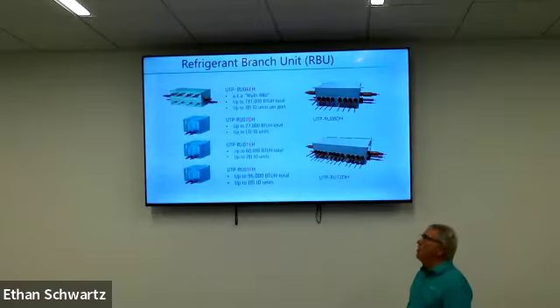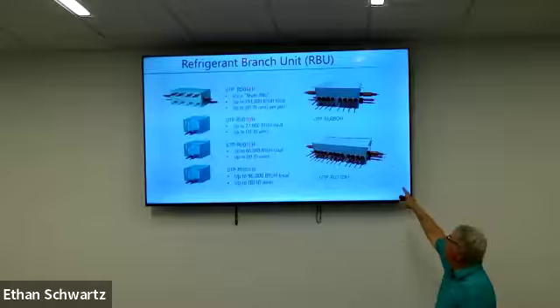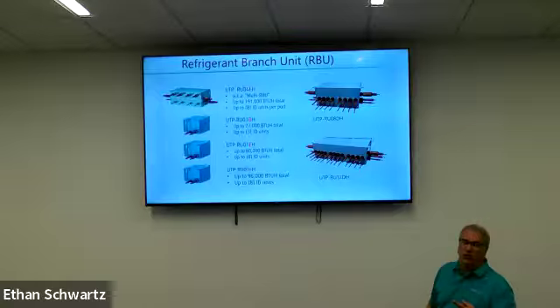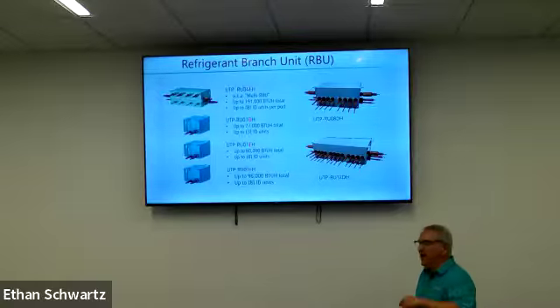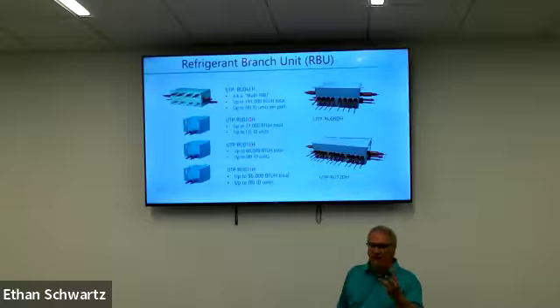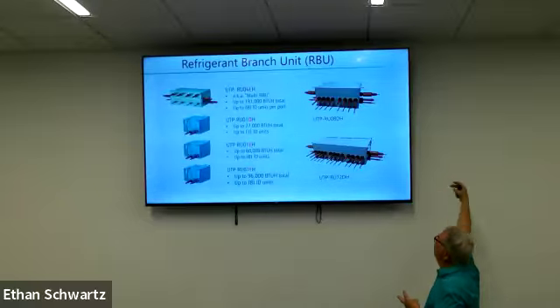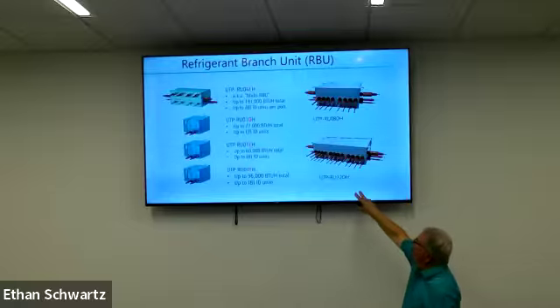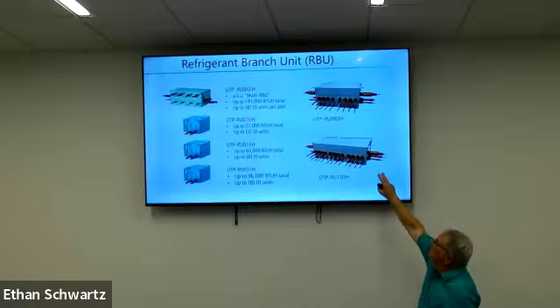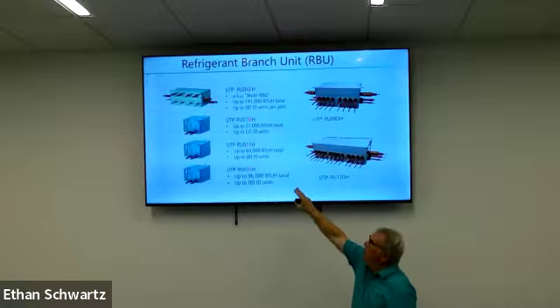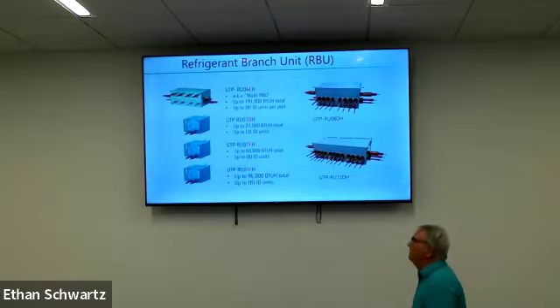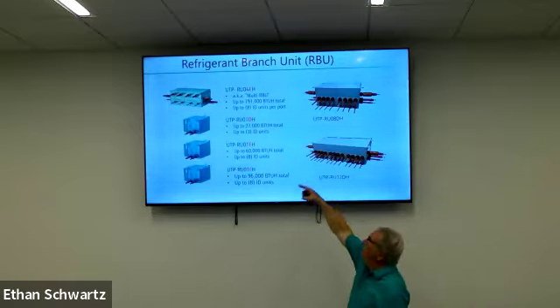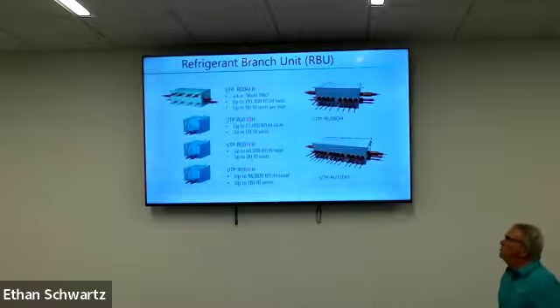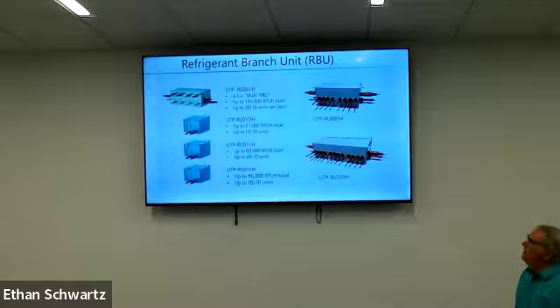So got to kind of figure out where is that RBU going to go. And as you see here, our system and every manufacturer except Mitsubishi is a three-pipe system. What does that mean? Like I said, liquid line, suction line, hot gas line from the outdoor unit. And we can come into one end of this. This happens to be a 12-port box. That is an 8-port box. We have 4-port, and then also single port if that's what's needed. Each one rated for a different number of total BTUs connected to the box and total number of indoor units that can be connected to it.